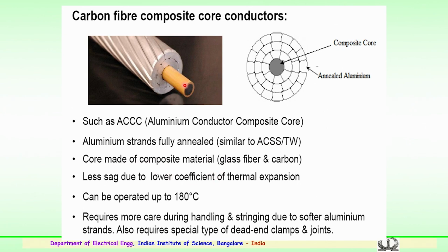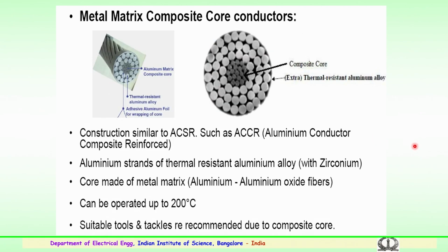This could be glass fiber and carbon. So, this also possesses less sag, operates at 180 degrees, and has a lower coefficient of thermal expansion like the earlier high temperature conductors. But this requires more care during handling and also during stringing of the line due to the softer annealed aluminum strands of the conductor. Having softer aluminum strands, it also requires a special type of dead end clamps and joints. So, this is the requirement for this type of composite core conductors.